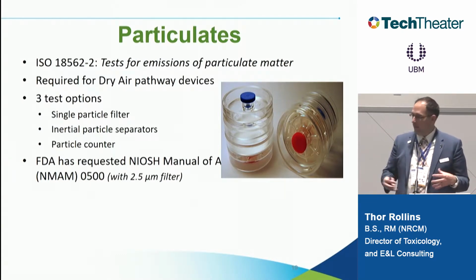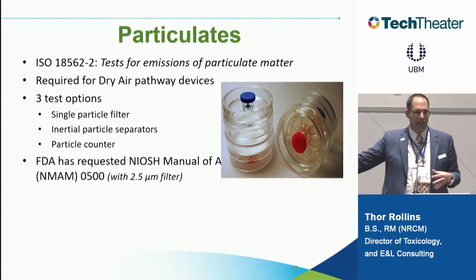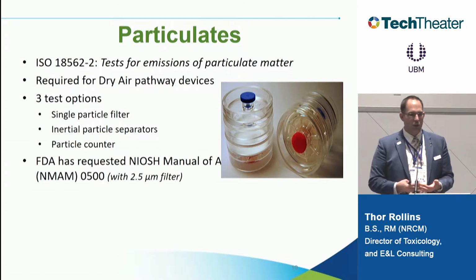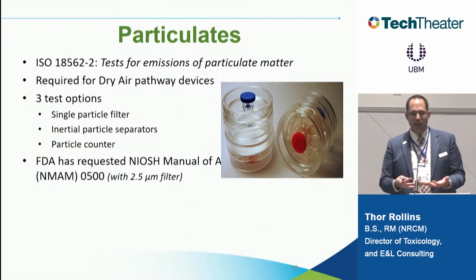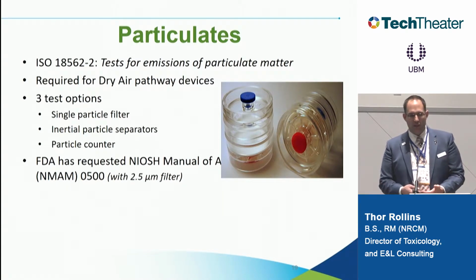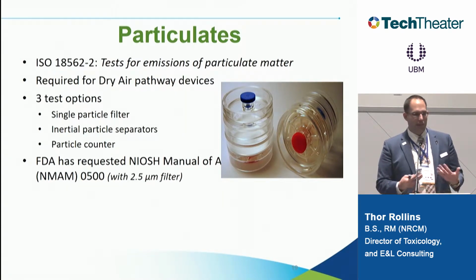So we actually have a different method that we can look at particulates by weighing them out with a very sensitive scale on a filter. So basically we run your device like it would normally be clinically run. We collect the particulates that are lodged on the filter, and then we weigh that filter difference. And this helps us evaluate the particulates that have been generated from your device.